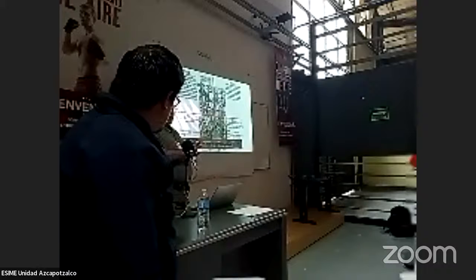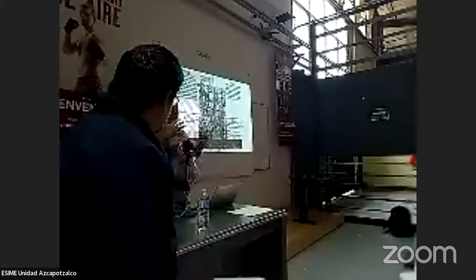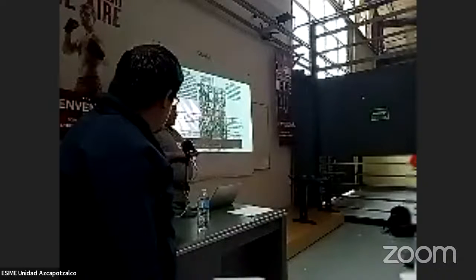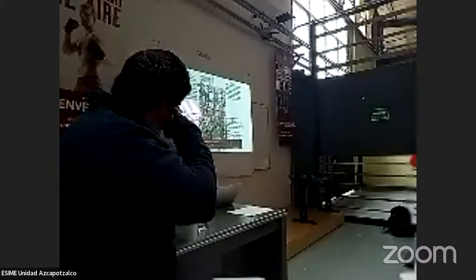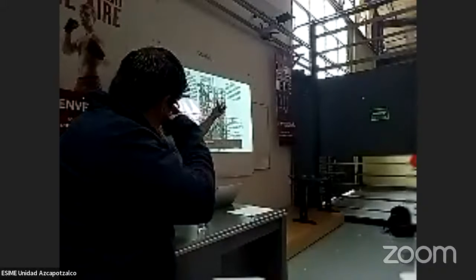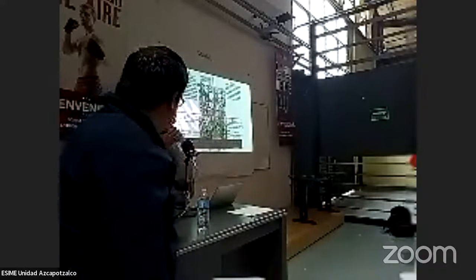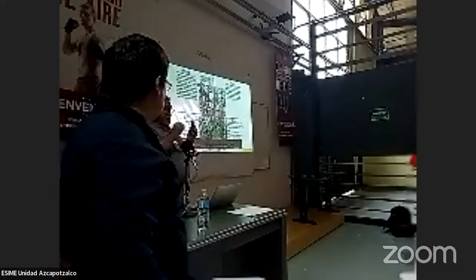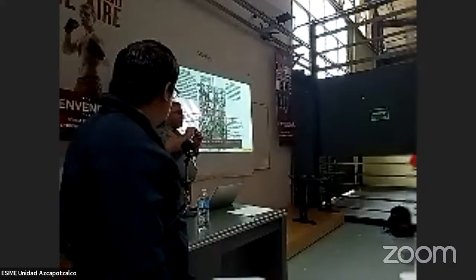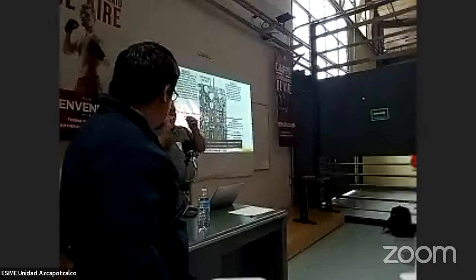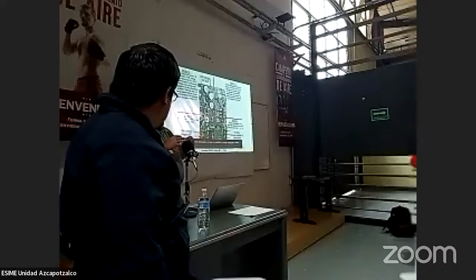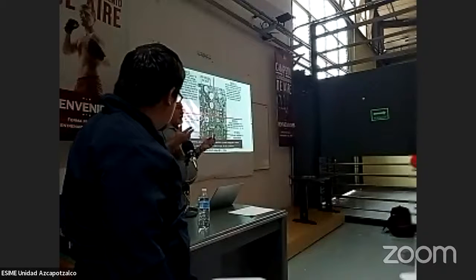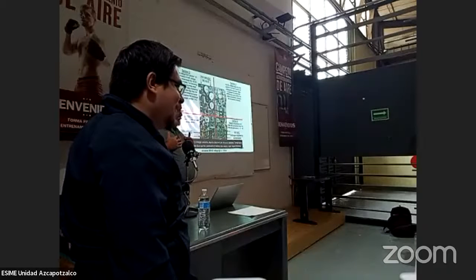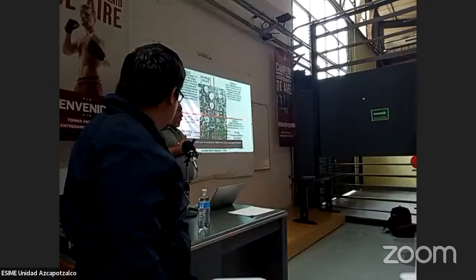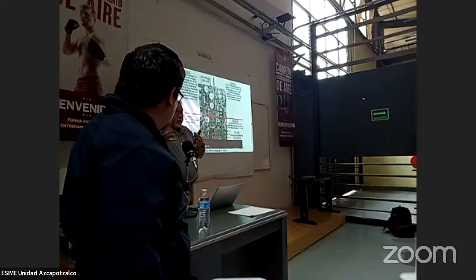There's a percentage of boards that we get back from people saying they were defective, and we find no fault. A very high percentage. A lot of times, especially in our country, the US, they change the board first just to see if that works. That's not the proper way to troubleshoot the system. Use your meter. You can find out if you have incoming power and outgoing power. Leave the board alone, it's not your board. I have people who call me and say, I've changed the board three times and it's still doing the same thing. And I say to them, all you've told me is it's not the board. Stop changing the board, right? Find your problem.